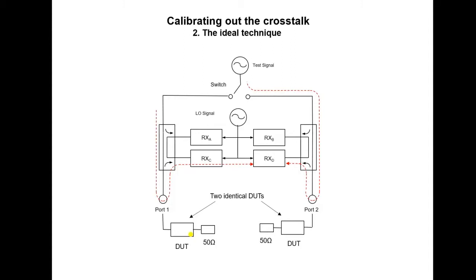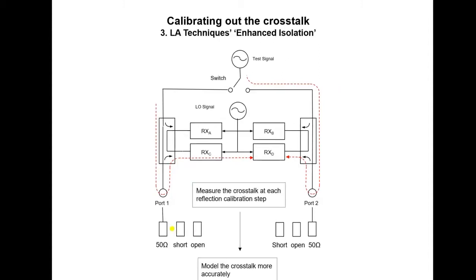Now let's look at a third approach which we use, or rather, is an option in the user interface software, and that is the enhanced isolation option. What we do is to take several crosstalk measurements and build a model to more accurately predict the crosstalk. When we do the calibration reflection measurements for 50 ohms, short and open, we also make a crosstalk measurement.